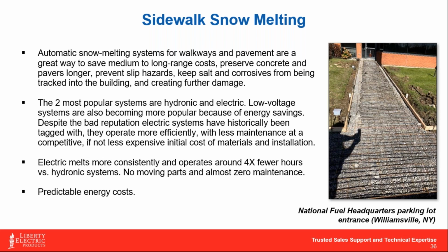And the electric systems have just far fewer moving parts. That is a huge comparison between the two, the fact that the electric system requires next to no maintenance over time. Another thing that I really like about the electric systems is that to figure out how much your operation cost is per hour, the math is very easy. Essentially, when we spec jobs across upstate New York, we're typically modeling them around 50 watts a square foot, which is the same as hydronic is doing at 150 BTUs. It's roughly about the same amount of heat.